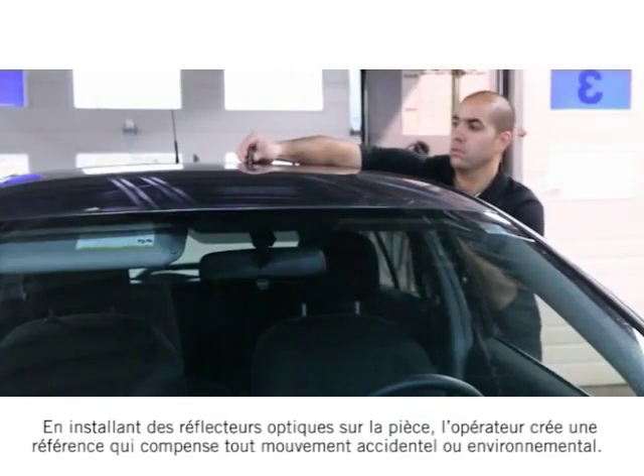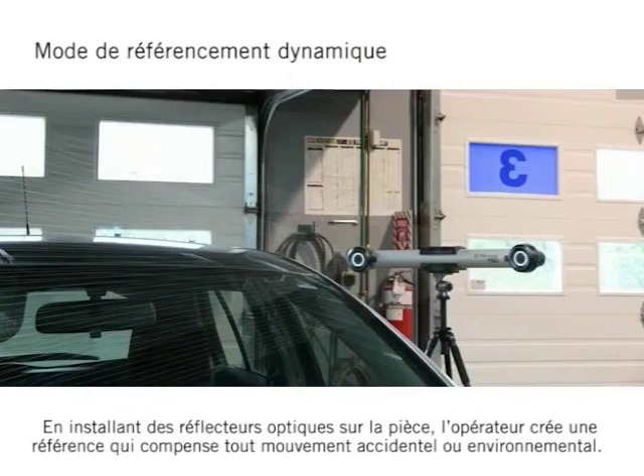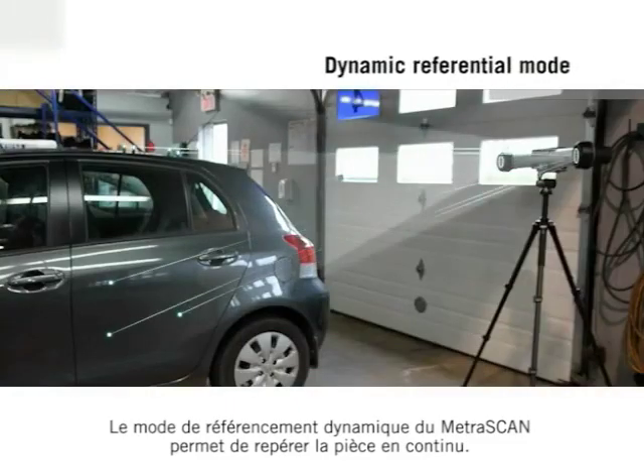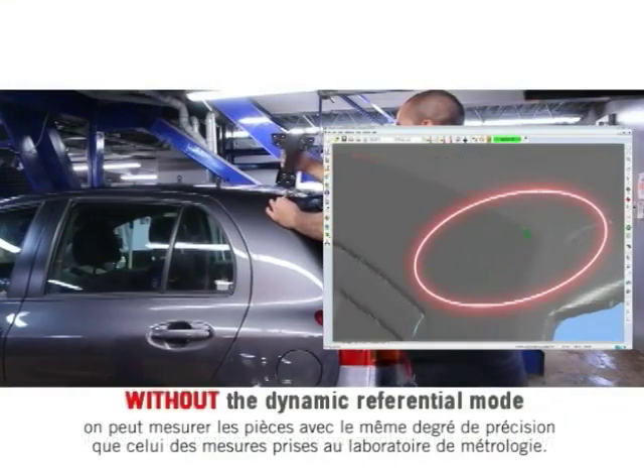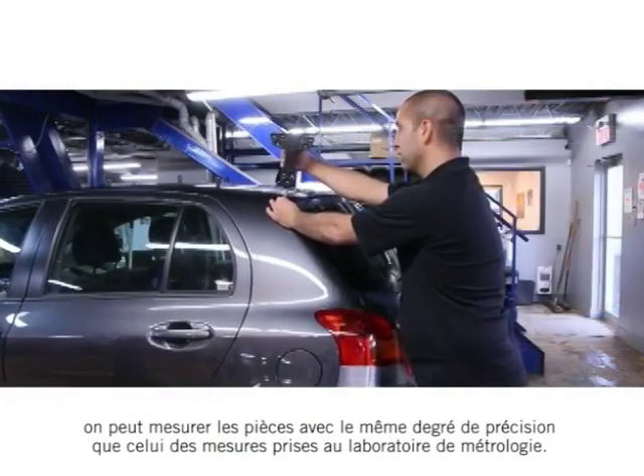By attaching the optical reflectors on the part, the operator creates a reference that compensates for any accidental or environmental movement. The dynamic referential mode of the MetraSCAN tracks the part continuously. With environmental dilemmas such as vibration solved, parts may be measured with the same degree of accuracy as if measurements took place in the metrology lab.